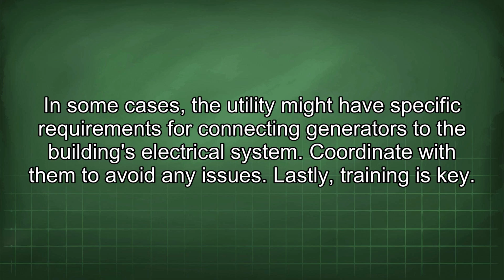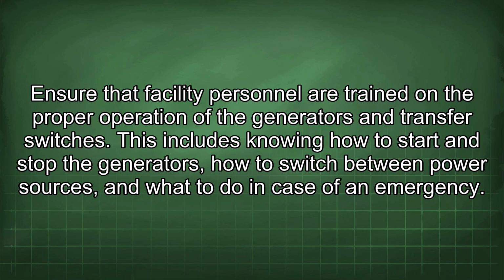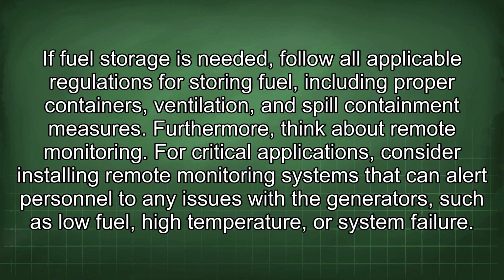Lastly, training is key. Ensure that facility personnel are trained on the proper operation of the generators and transfer switches. This includes knowing how to start and stop the generators, how to switch between power sources, and what to do in case of an emergency. If fuel storage is needed, follow all applicable regulations for storing fuel, including proper containers, ventilation, and spill containment measures.